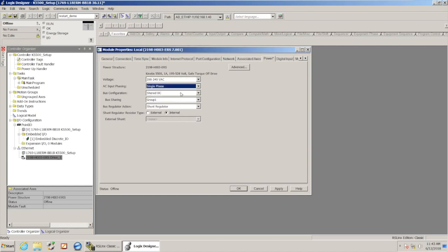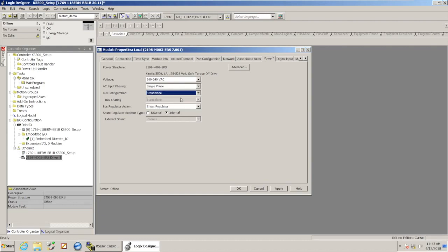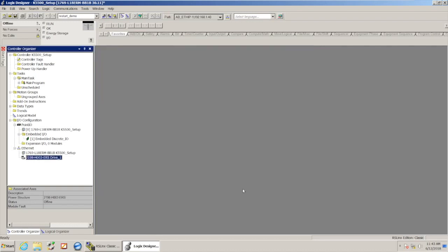Also, for the bus configuration, in this instance, these are set up as standalone drives. If you had DC busing, you would set that up there. And I'm going to leave the shunt regulator as internal, and I'm going to say apply, click OK, and now I've updated my power settings for that drive.